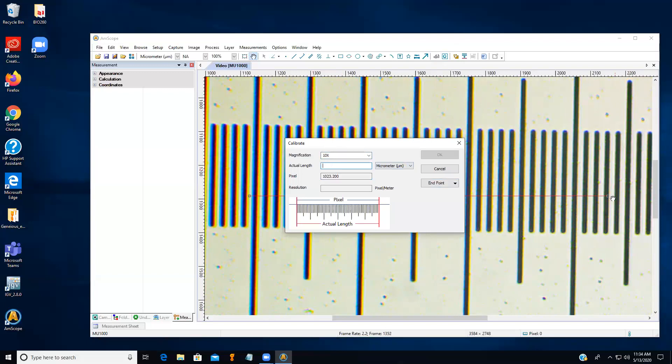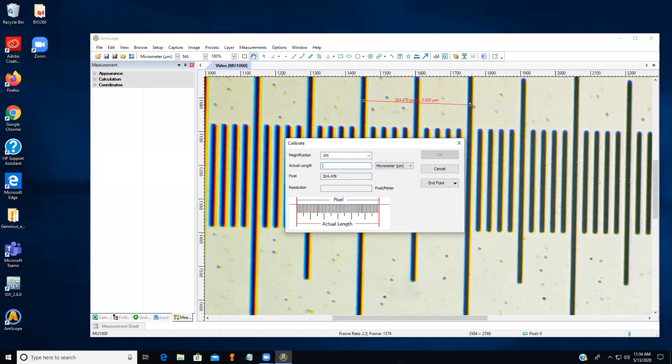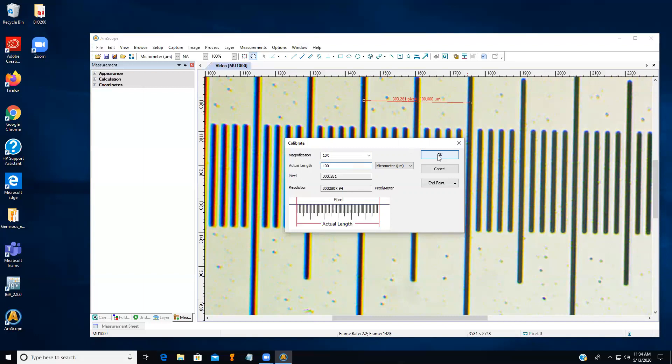You might need to adjust the light a little bit. You might need to use a little bit more fine focus to fully focus on the scale bar. And go back into calibrate. Now we're at 10x. And our line appeared here again. So adjust it again. And here, these are now much bigger, of course. So try to be as in the center of the width of that line as possible, and again, as perpendicular to those lines as possible, so it really is as precise as it can be. And as we remember, this is 100 micrometers. So I'm going to say okay. It's going to give me an error. It shouldn't give an error to you because you haven't done this yet.